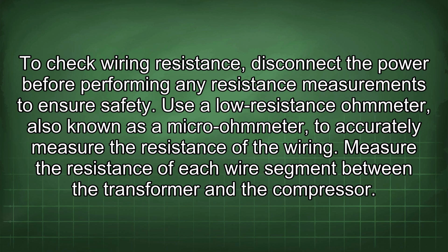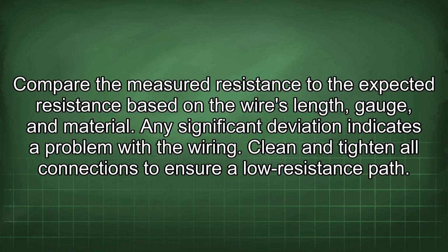To check wiring resistance, disconnect the power before performing any resistance measurements to ensure safety. Use a low-resistance ohmmeter, also known as a micro-ohmmeter, to accurately measure the resistance of the wiring. Measure the resistance of each wire segment between the transformer and the compressor. Compare the measured resistance to the expected resistance based on the wire's length, gauge, and material. Any significant deviation indicates a problem with the wiring.